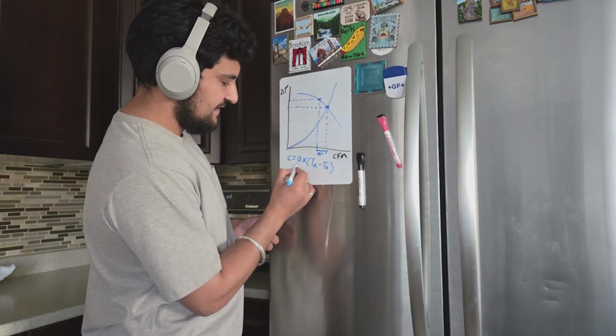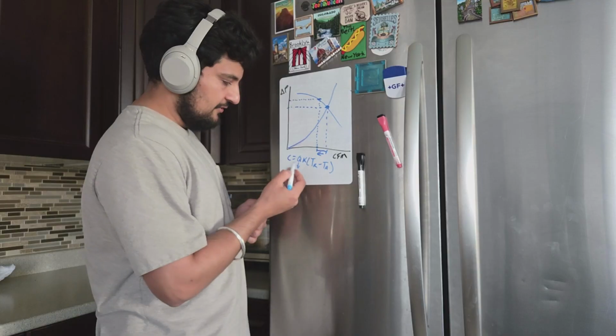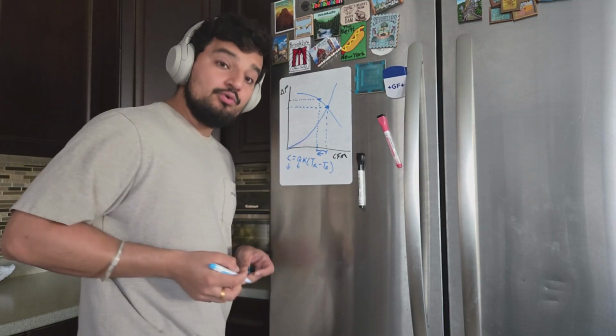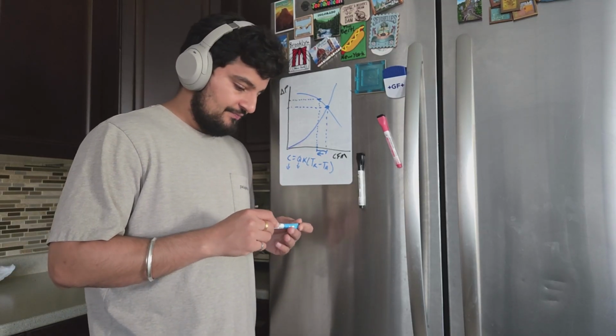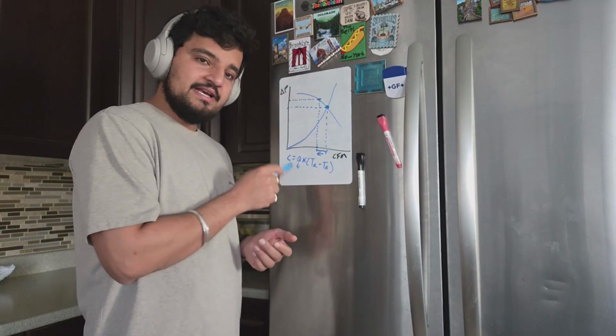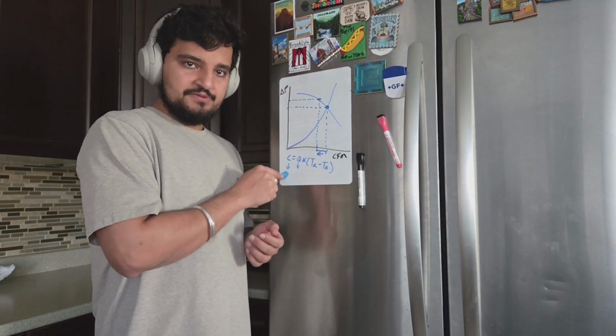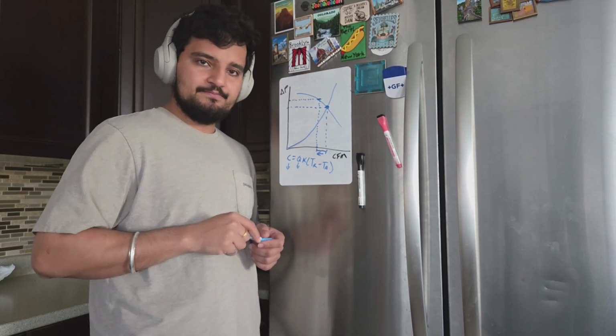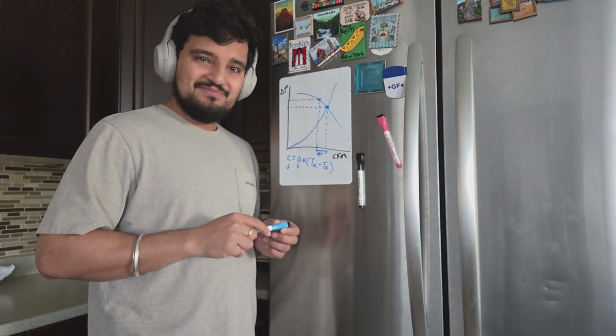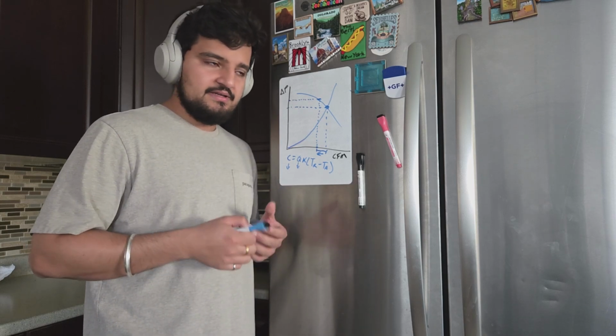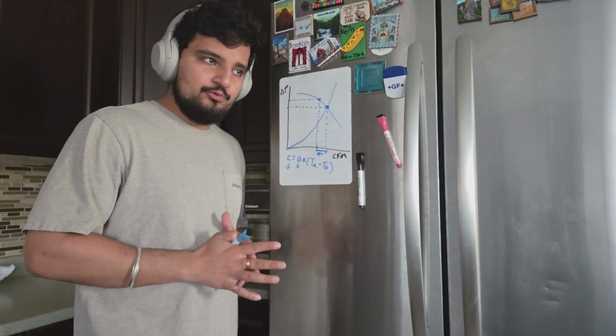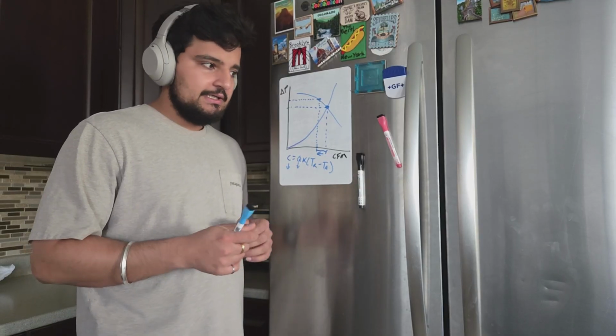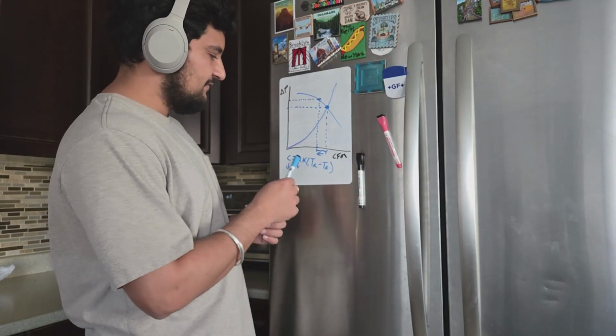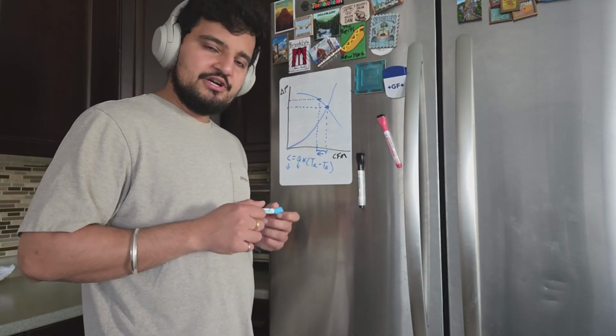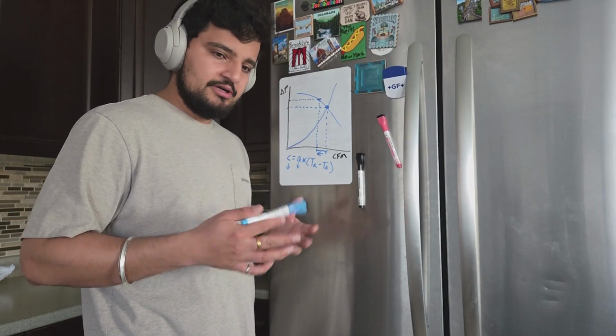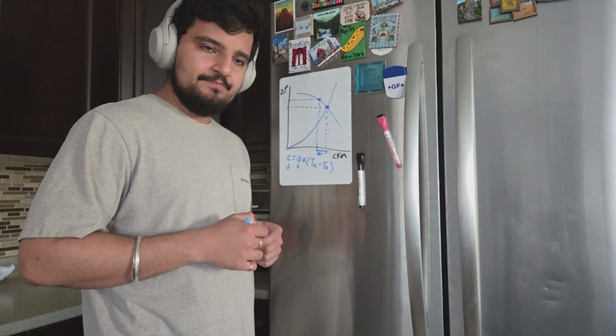So look, you've decreased your flow rate, which means you've decreased your cooling capacity. So now your air handling unit is delivering less air into the room, which means it's providing less cooling capacity for that room, which means the original design is no longer applicable and probably your room will be a little bit hotter than designed. And in order to fix this, you have to reduce the pressure drop across the ductwork and get it back to nominal.